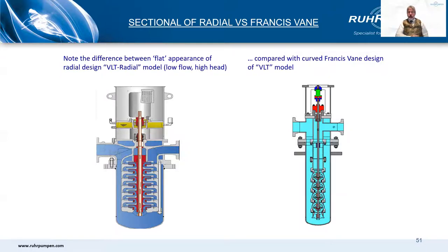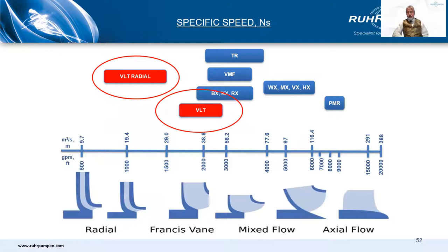European designs tend to be shorter and bigger diameter than their American counterparts. They also have flatter curves with a 25% typical head rise compared with about 40% for the Francis Vane. Ruhrpumpen has both designs available — our German heritage radial design and our American heritage Francis Vane design — so we can offer the best fit for any given situation.